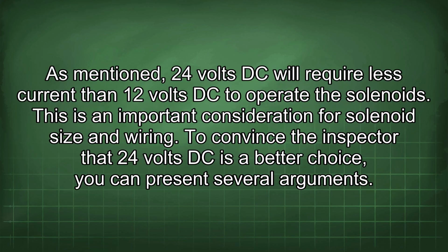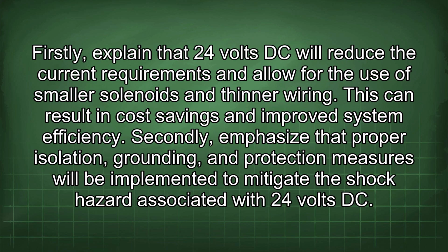As mentioned, 24 volts DC will require less current than 12 volts DC to operate the solenoids. This is an important consideration for solenoid size and wiring. To convince the inspector that 24 volts DC is a better choice, you can present several arguments. Firstly, explain that 24 volts DC will reduce the current requirements and allow for the use of smaller solenoids and thinner wiring. This can result in cost savings and improve system efficiency.